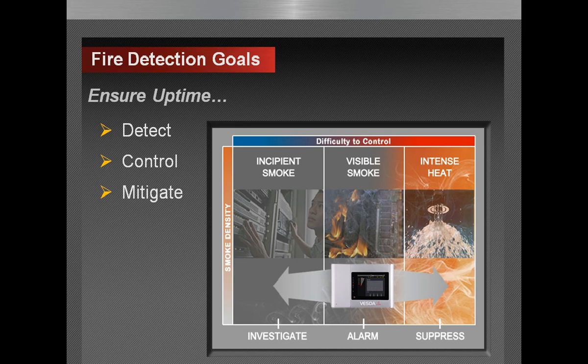There are 4 stages to fire development, and that is the incipient stage, the growth stage, the fully developed stage, leading up to the decay stage. Now, of course, the opportune time to respond is in this incipient phase of fire growth development prior to flame and prolonged smoke contamination. It's this stage that makes the difference between turning what would be a firefighting exercise into potentially a maintenance task. Of course, an ideal detection technology would be one that can monitor the entire progression of fire development, providing alarm thresholds at each stage, allowing for staged response leading up to the reliable initiation of suppression systems.